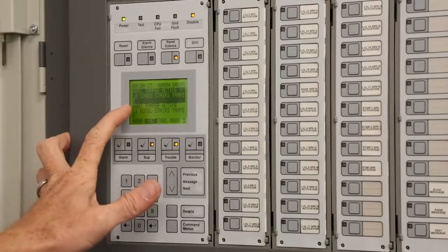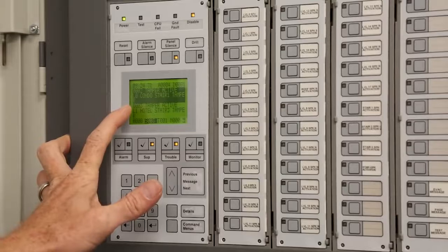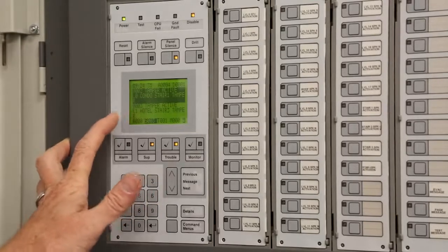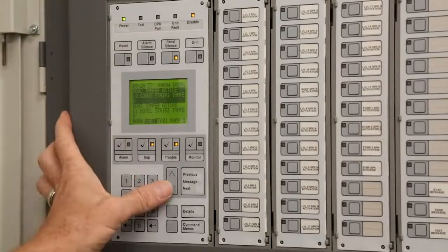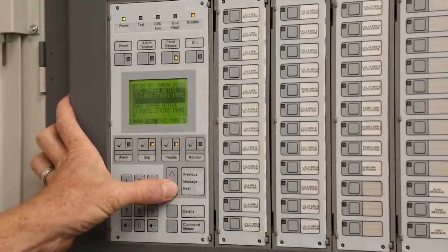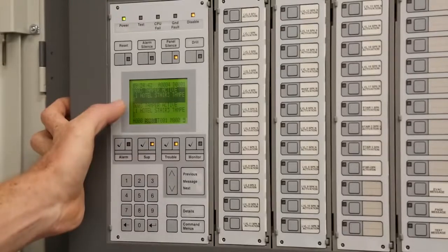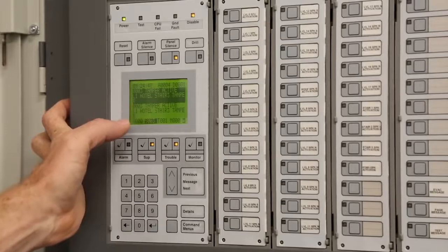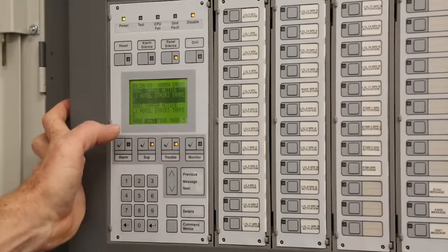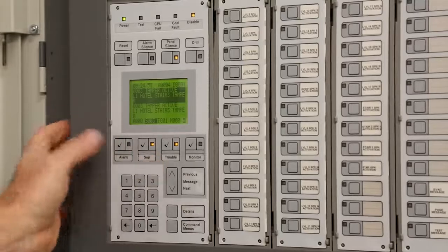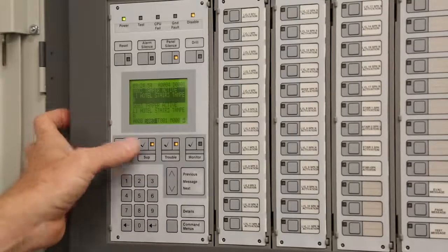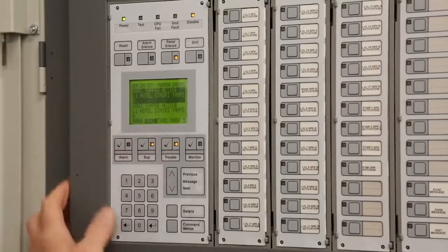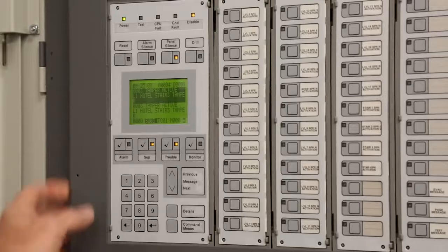So level 0, we call it condo side. Remember, this is only coming up on here, so don't worry about the VO portion of it, it's only showing up in the display. So that valve is shut off, and last but not least, the level 1 hotel is shut off too. They're working on them currently right now. So that's your supervisory. Again, you can hit anything you want here and scroll up and down, and that'll show you if it's an alarm condition, okay?